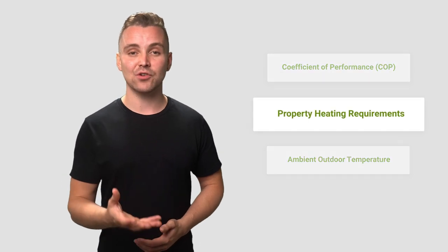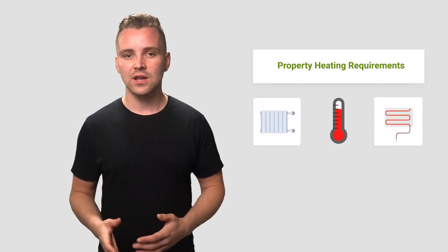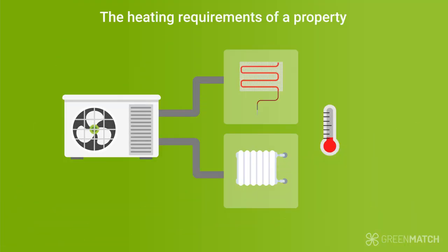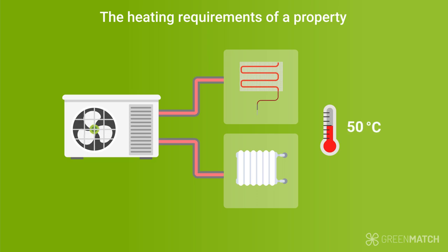Now let's talk about the heating requirements of a property. This is essentially the temperature the water in your radiators or underfloor heating needs to reach in order to heat your home effectively. The majority of air source heat pumps are at their most efficient when providing water at a temperature of 50 degrees within a central heating system. However, many UK homes with older, traditional radiators will have a heating requirement of at least 65 degrees, meaning a heat pump will need to work harder and its COP will go down.